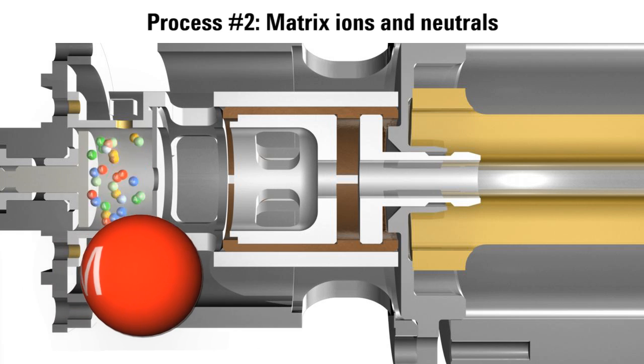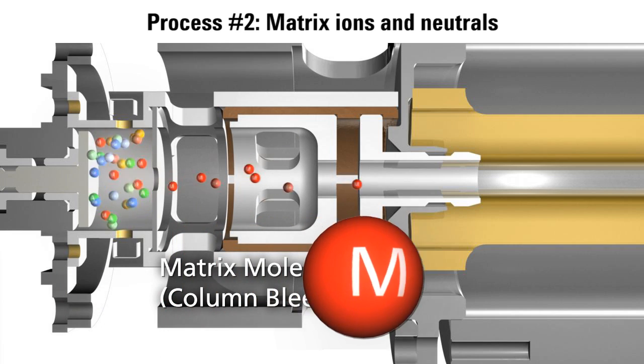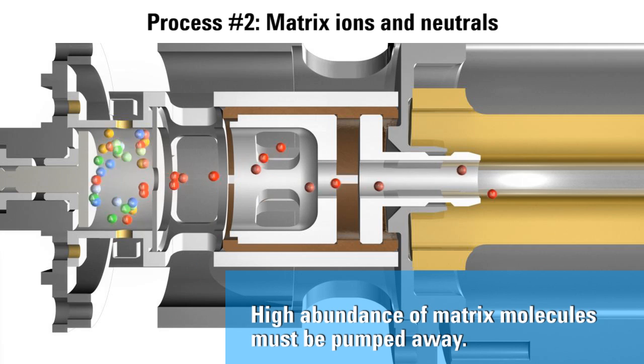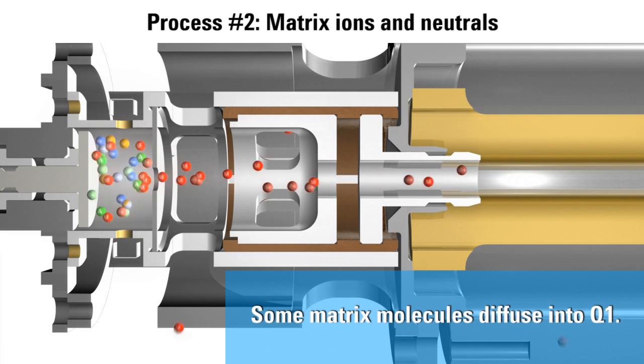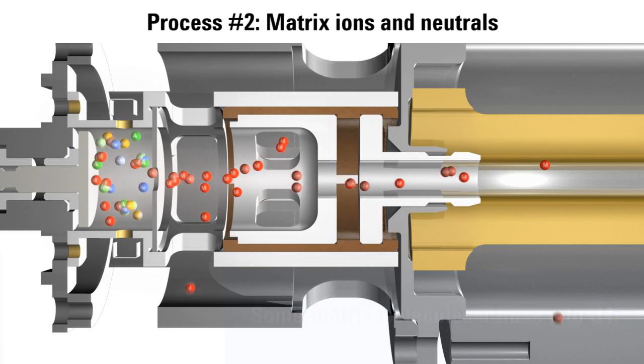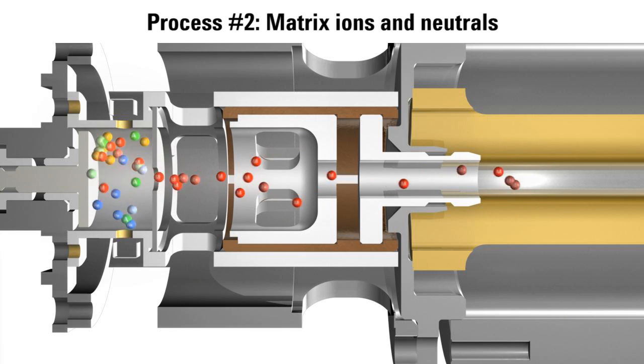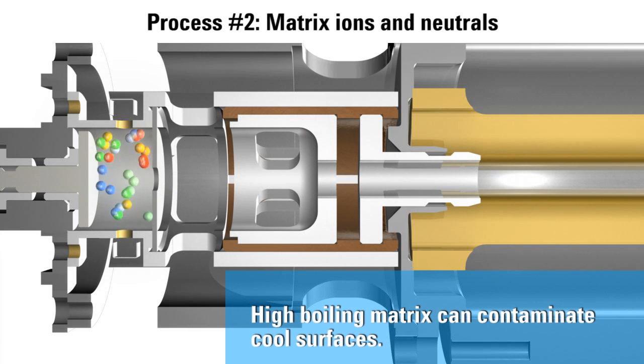Again we ask, what about the large population of non-ionized molecules? Although the turbo pump removes many neutrals quickly, some will randomly diffuse into the quadrupole. At the end of the GC separation, the EI source will be flooded with the highest boiling molecules from the sample matrix. Even in a vacuum, these high boiling molecules can contaminate surfaces in the mass spectrometer. A cool surface will accelerate this contamination process.